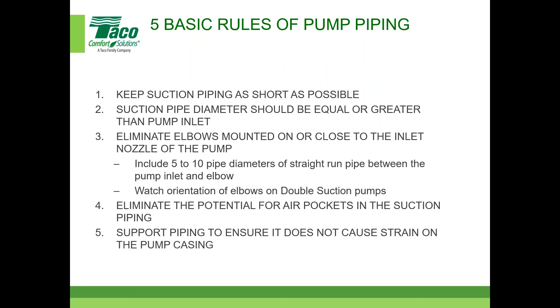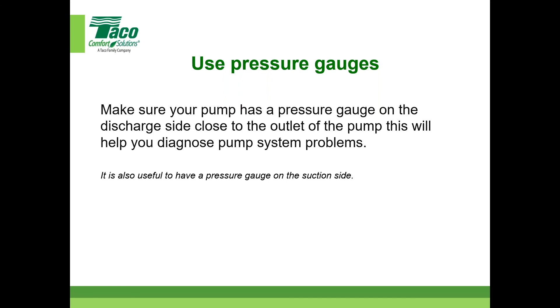Pressure gauges. I don't think you can have enough of them, right? You just can't have enough pump pressure gauges, as close to the suction and discharge, at least on one side. We can't emphasize that enough. Put it in your MEP drawings, put it in your details, add it in there. Sooner or later, there's a good possibility on a project, maybe not every project, but on a project, you're going to need that information, or somebody's going to need that information. And it's easier if it's there, right? You don't want to start changing things once it's in the field. So, stuff to consider.